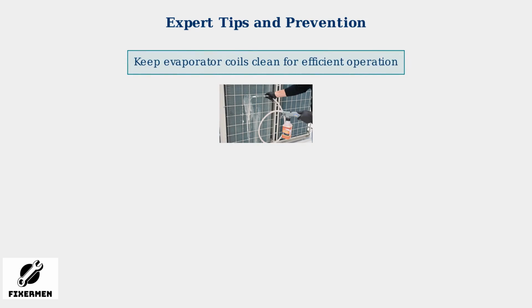Dirty evaporator coils can significantly impact your AC's efficiency. Regular cleaning ensures proper heat exchange and prevents the system from overworking. Clean coils help maintain optimal refrigerant pressure, directly reducing the chances of triggering the E8 overload protection.